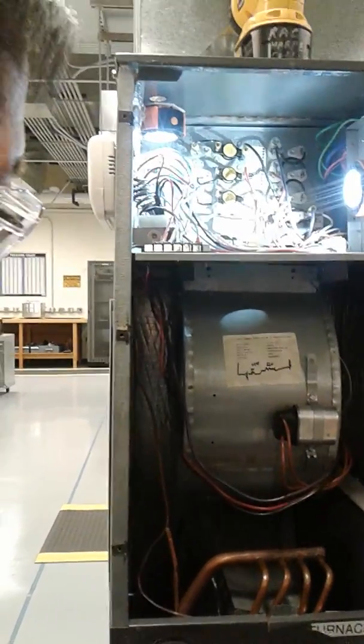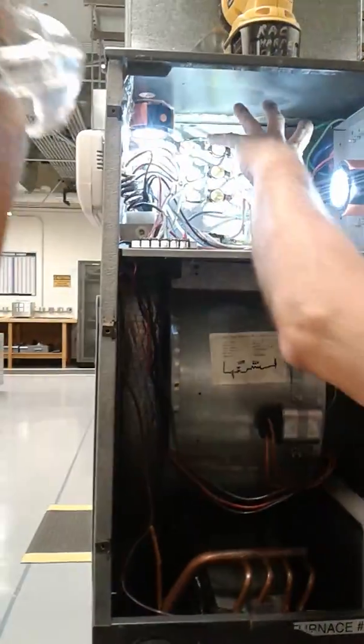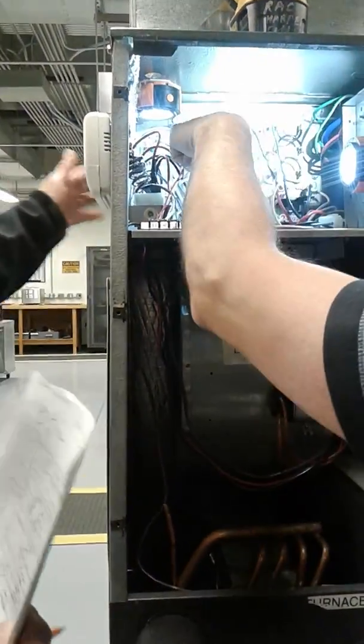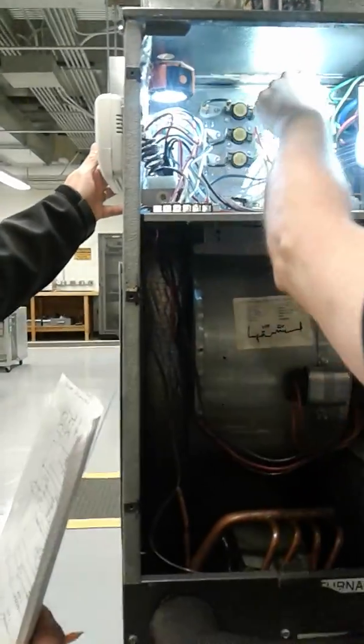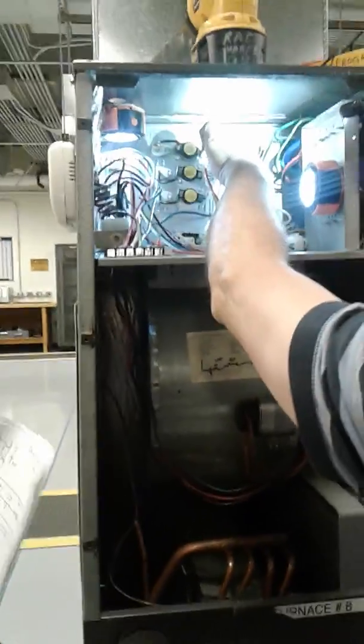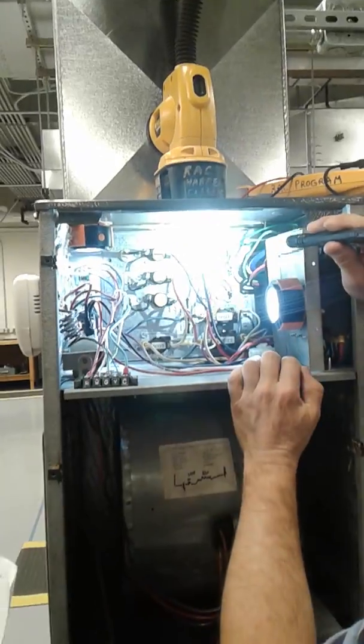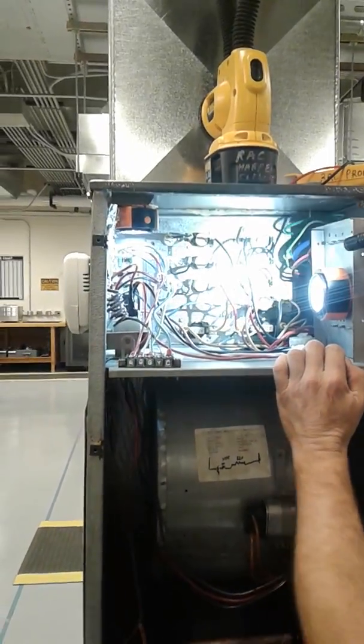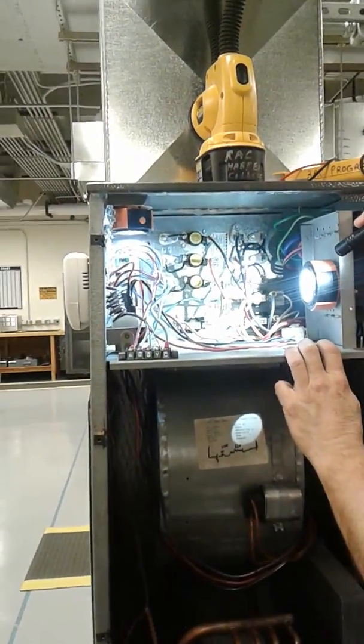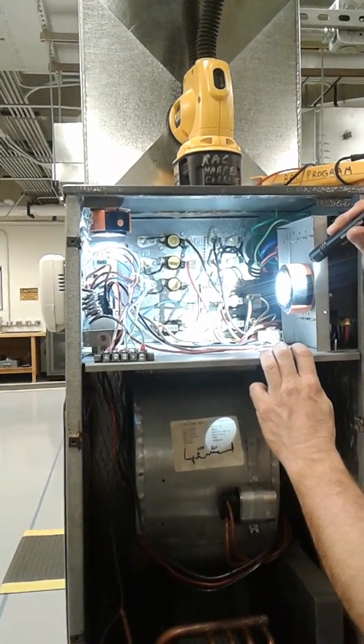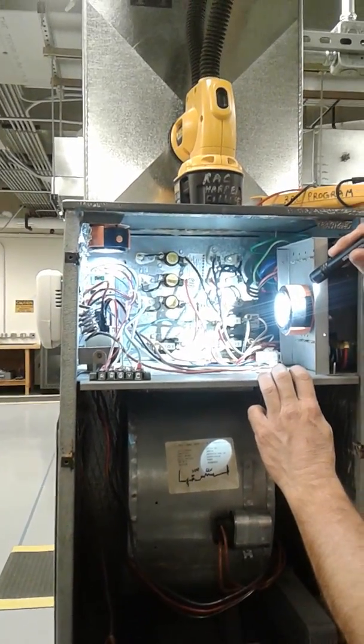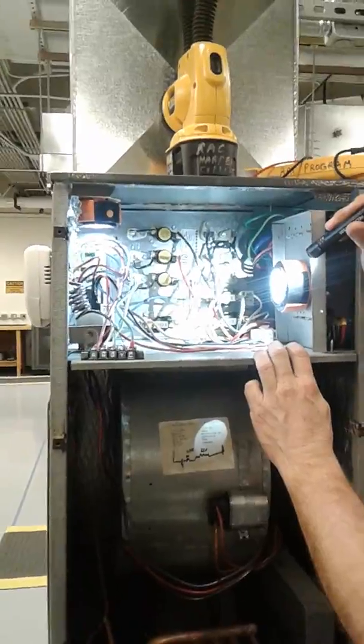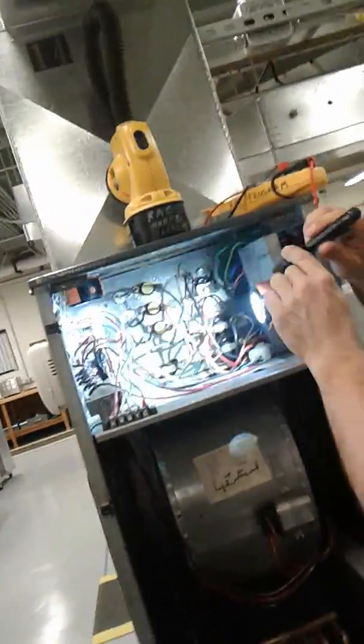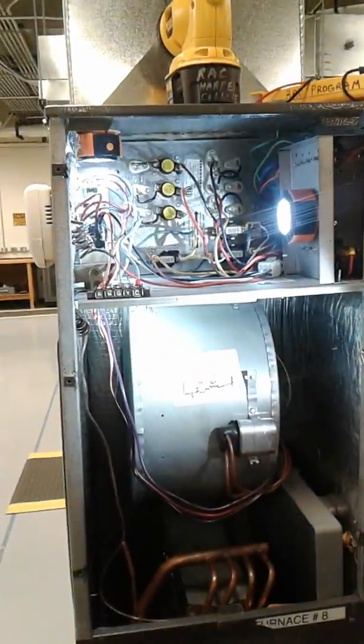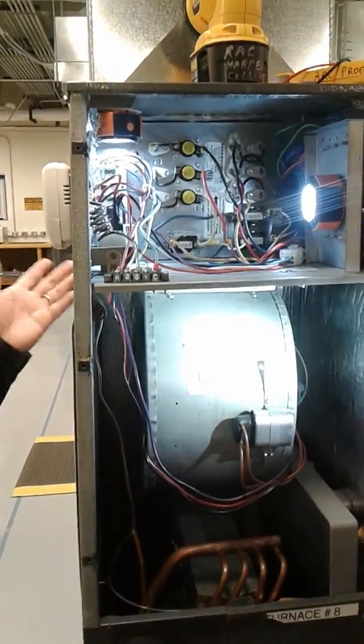Okay? So where's the heat exchanger now? The heat exchanger is right here. It's all right there. This is the heat exchanger inside. You don't see it. And another thing you don't see is the fusible link because it's inside that chamber. So if it's an electric furnace, we do not have the task of cleaning the clamshell. Oh no! It actually doesn't have a heat exchanger, no need for maintenance. Less maintenance. It's sometimes less maintenance.